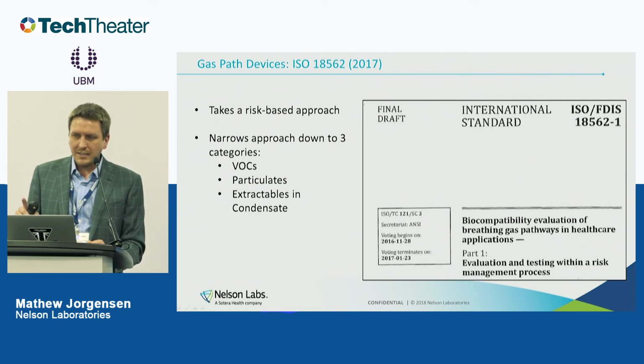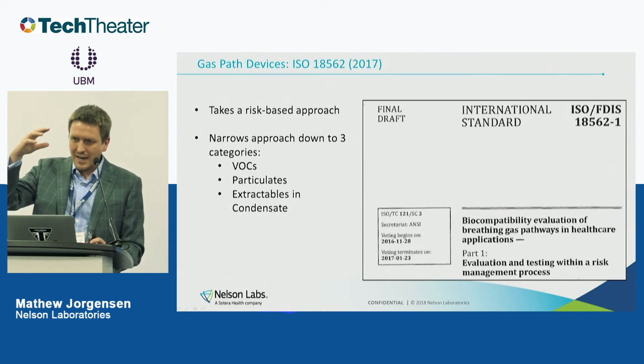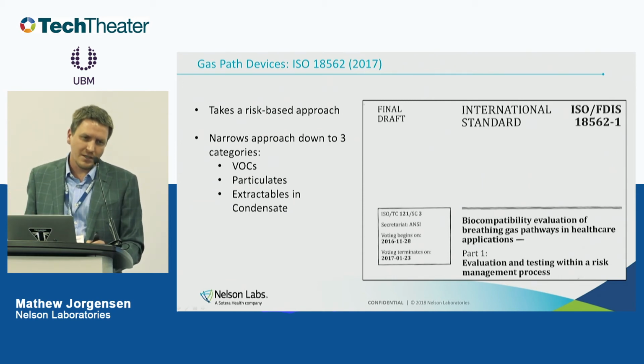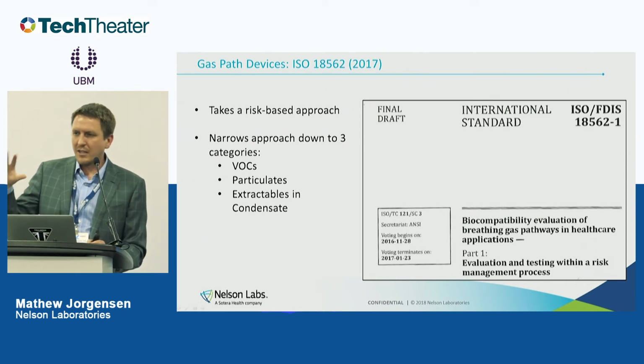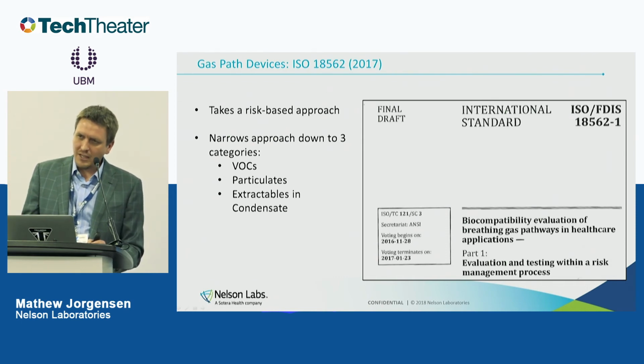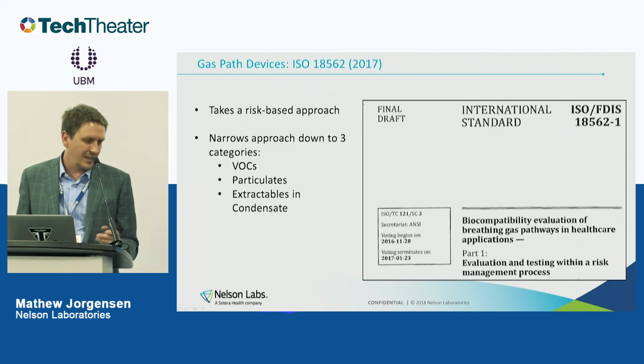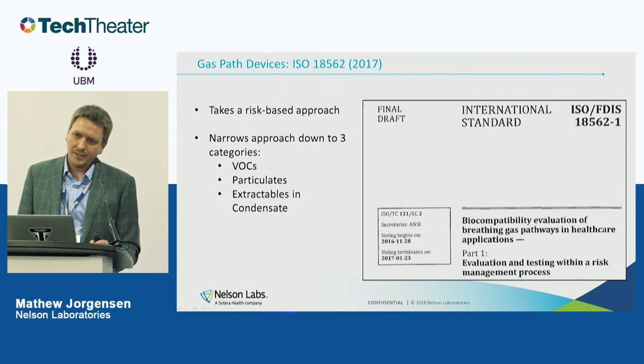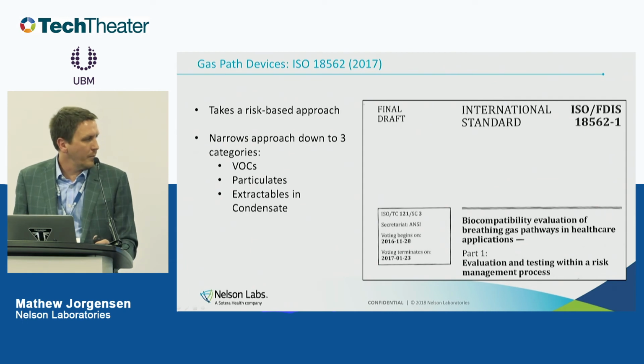If you have a device, something like a breathing circuit where water can condense inside and then that liquid can run into the patient, that's a separate thing. Then you need to understand what could leach into that liquid that the patient could swallow. So in that case, you end up doing extractables and leachables chemistry testing like I described before.